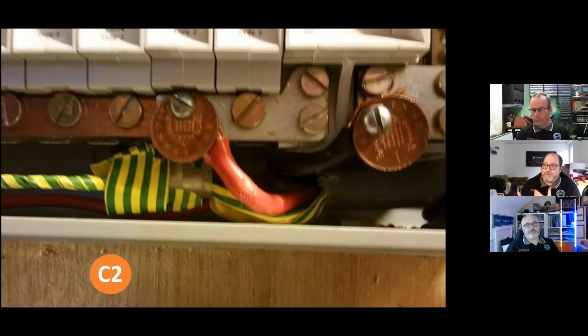Do you think that's okay with the ethical standards that we've been reading so far? To be honest with you, before I put the lid back on, I'd get the homeowners. Even if I had to wait for them to come home and explain to whoever the owner of the house was, or get the landlord down and say, listen, this really needs fixing now. This is just a ticking time fire, basically waiting to happen. And effectively, I would only put the lid back on if I was coming back to do the board change, to be perfectly frank. I would definitely issue a danger notification.